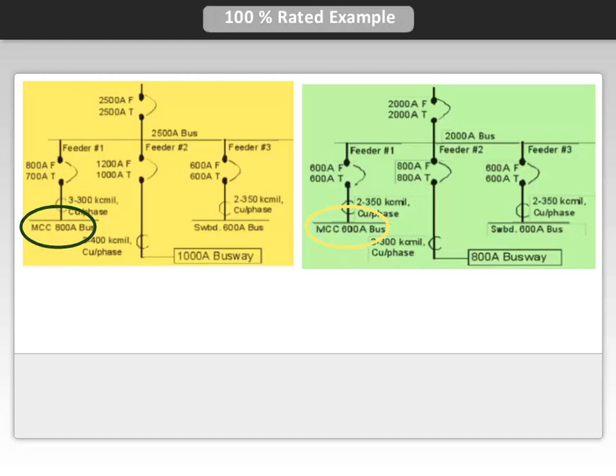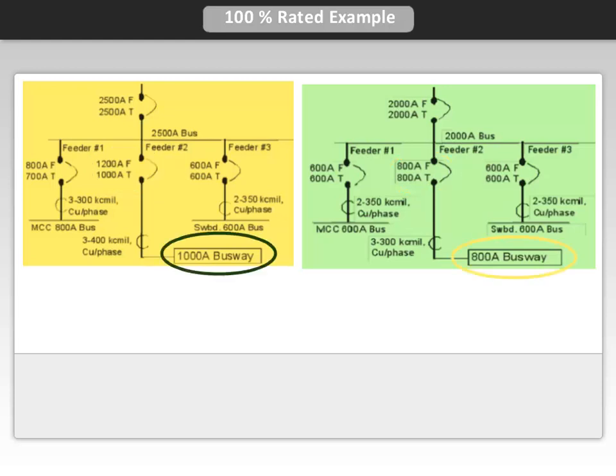Feeder number 2 had a load of 800 amps. We can now use an 800 amp 100% rated breaker, but once again we now use an 800 amp busway instead of the 1,000 amp busway. Feeder number 3 carries 600 amps total, so using a conventional sizing method, there is no need to use a 100% rated breaker here.